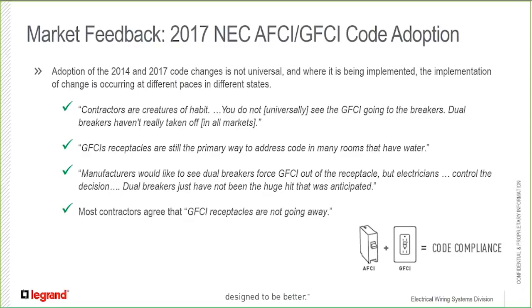Next quote, GFCI receptacles are still the primary way to address code in many rooms that have water. Next quote, manufacturers would like to see dual breakers force GFCI out of the receptacle, but electricians control the decision. Dual breakers just have not been the huge hit that was anticipated. And finally, most contractors agree that GFCI receptacles are not going away. So again, this is the culmination of research of electrical contractors and electricians throughout America. So basically, they're still fans of the GFCI receptacle, and that's what we want to talk to you about today.